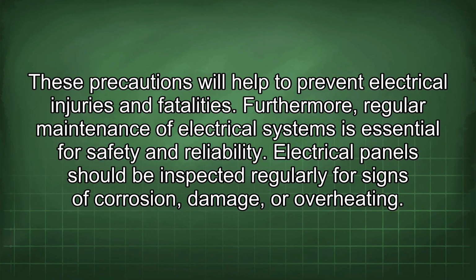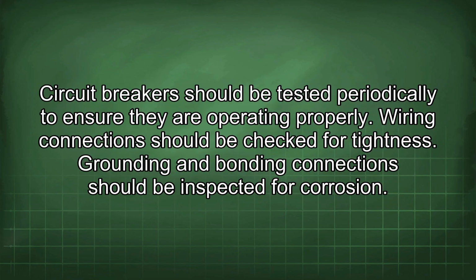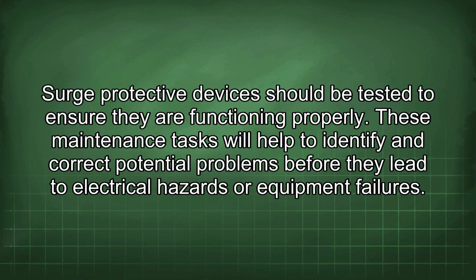Furthermore, regular maintenance of electrical systems is essential for safety and reliability. Electrical panels should be inspected regularly for signs of corrosion, damage, or overheating. Circuit breakers should be tested periodically to ensure they are operating properly. Wiring connections should be checked for tightness. Grounding and bonding connections should be inspected for corrosion. Surge protective devices should be tested to ensure they are functioning properly. These maintenance tasks will help to identify and correct potential problems before they lead to electrical hazards or equipment failures.